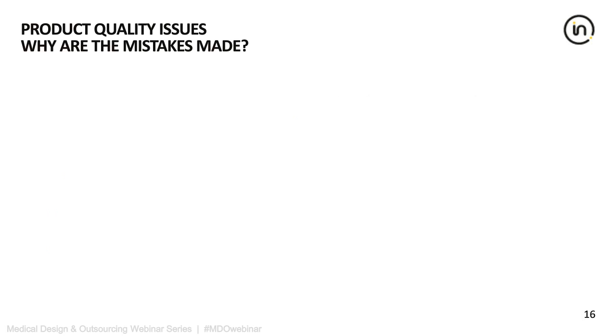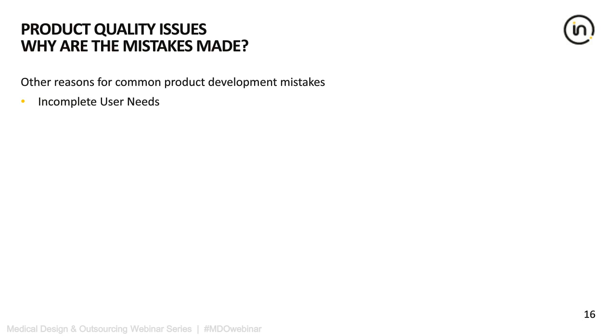So some other reasons that common product development mistakes are made: incomplete user needs. If you don't understand what your user needs, how can you deliver exactly what he wants? Also, an incorrect translation of user needs into product specifications. Your user need is the voice of the customer, and you need to turn that into engineering specifications that you can measure and verify performance against. But if you don't do that accurately, you might either have a measurement that can't be done, or it's subjective, or you might have a measurement where you've set the bar too low relative to what the user need is. And so that translation activity is critical for success.